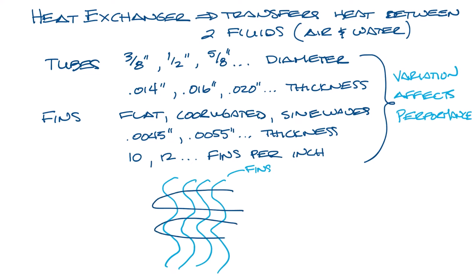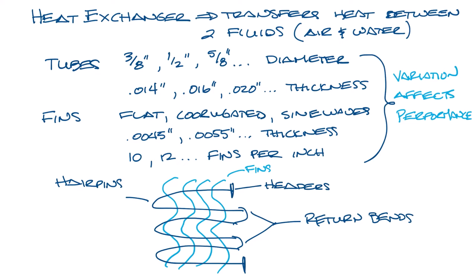The copper tubes are bent into hairpins and inserted through the fins. Each hairpin is connected to the next hairpin by a return bend that is welded on to make a continuous flow of water through the coil. The headers, also known as manifolds, are where your supply water and return water piping is connected to the water coil.